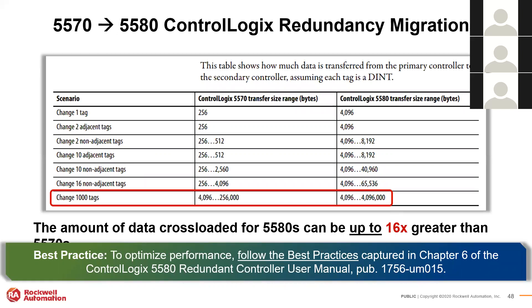An example from the manual shows the difference in how much data is used during cross-loading. In a 5570, the range is 4096 up to 256,000 bytes depending on efficiency. If the controller's data management is not efficient, the amount of data transferred during cross-loading can increase significantly. This wraps up the presentation — anyone implementing a 5580, new or migrating, should keep these best practices in mind to get the best result.